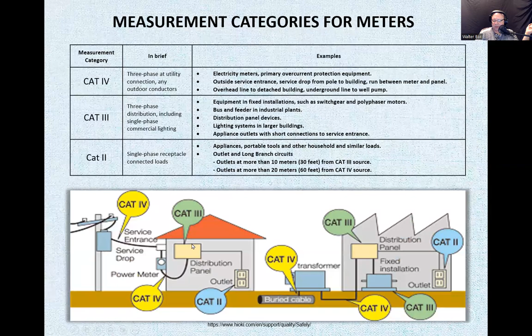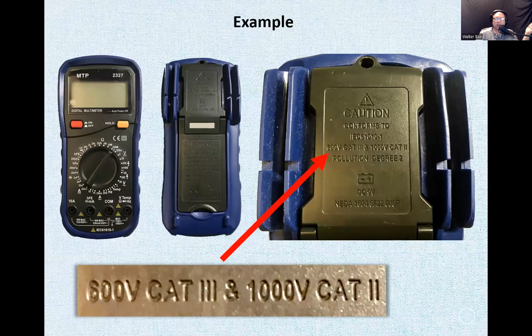Now, let's see the next. How can you tell which category your multimeter, the one that you have, right? I think it's this one here or maybe a similar one. The information should be somewhere there. Like, for example, here at the back, I just took a picture of that and I zoomed in. What does it say here? You can measure up to 600 volts if you're dealing with Cat3 sources, category 3 sources. Or you can measure up to 1000 volts if you are measuring category 2 source. Category 2 source up to 1000 volts. And here is the rules, sort of. And here is a category 3 source. So here is how you can read the specifications on your thing.